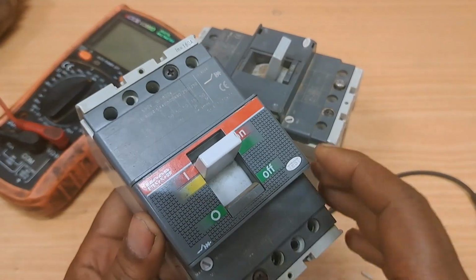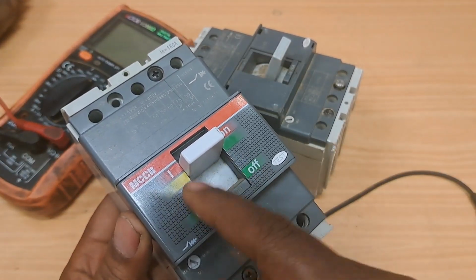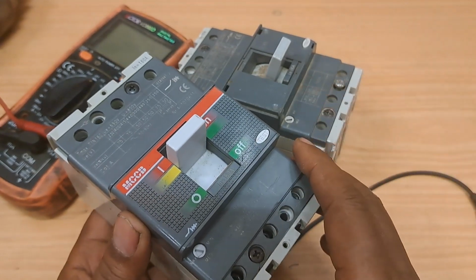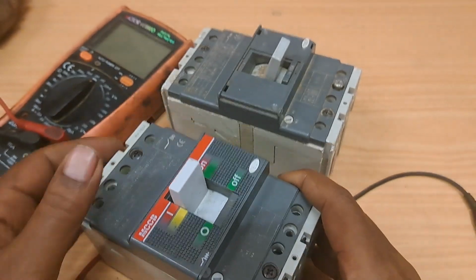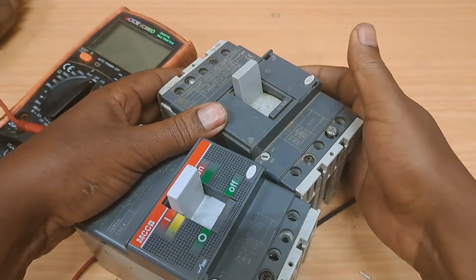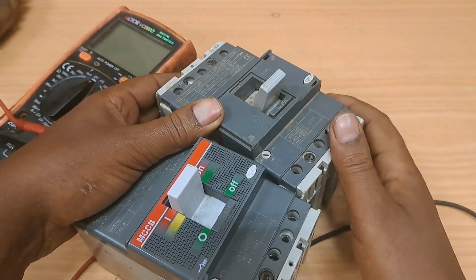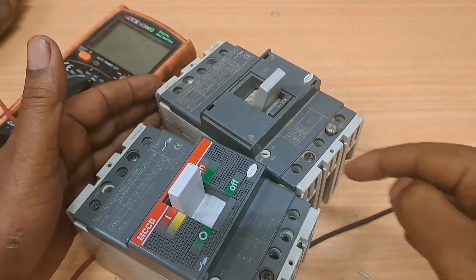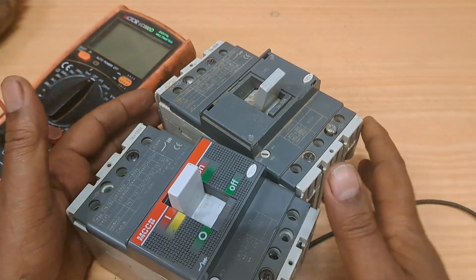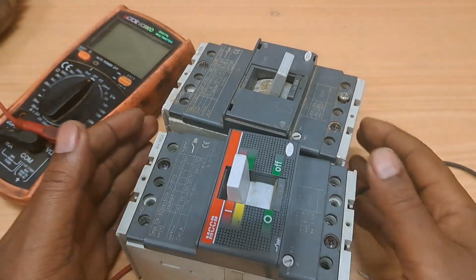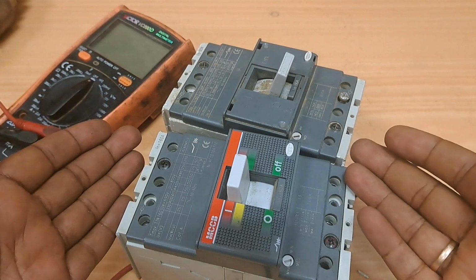Irrespective of the current value, whether the current value is higher or lower, the test procedure is the same. Physically inspect, make sure that it snaps with a strong closing and opening force, make sure that you have continuity, and make sure that there is no short circuit. This is how you can simply check operation of a circuit breaker.